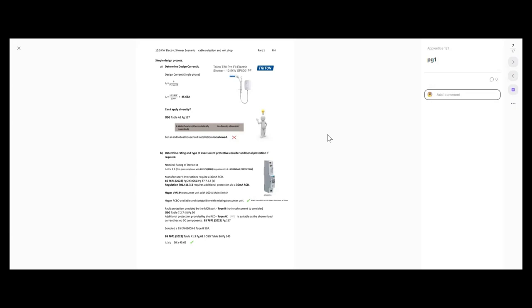Within the regs on page 243 and the on-site guide on page 87, we've got information regarding this type of installation. Because it's going to be installed in a room containing a bath or shower, we've got to consider regulation 701.411.3.3 — it is a requirement that it is protected with additional protection by a 30 milliamp RCD. The Hager board is just a 100 amp main switch board with no RCDs in it. So we need an RCD, and we also need to think about overcurrent protection, so we're going to go with an RCBO.